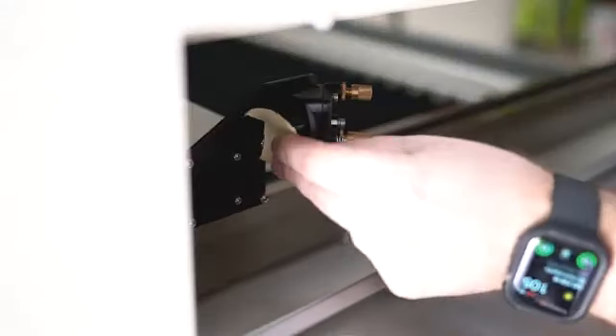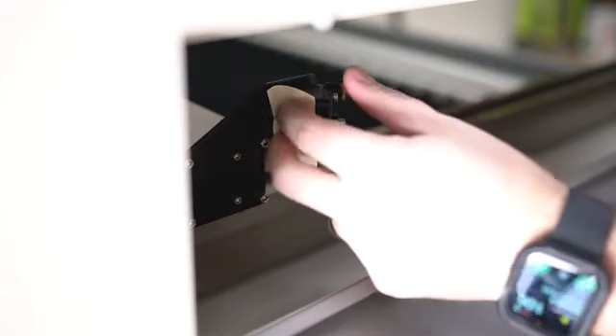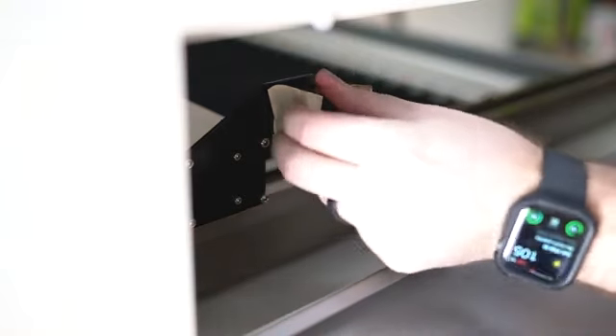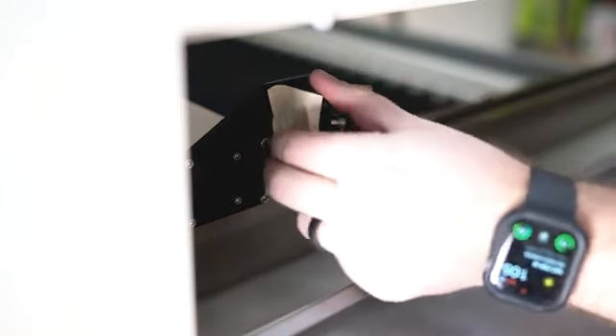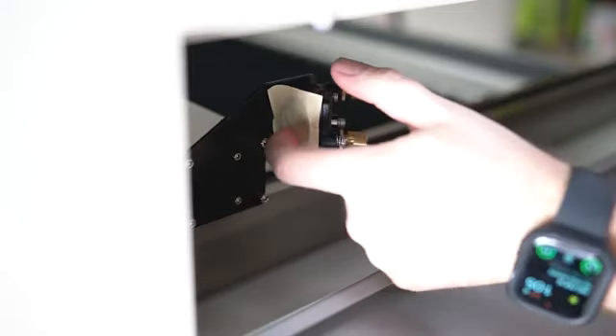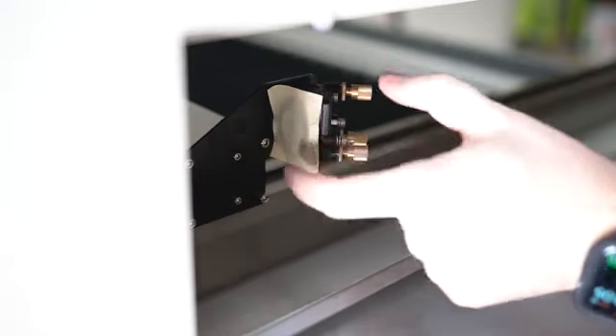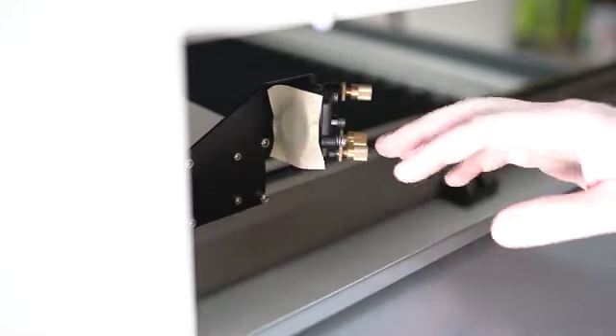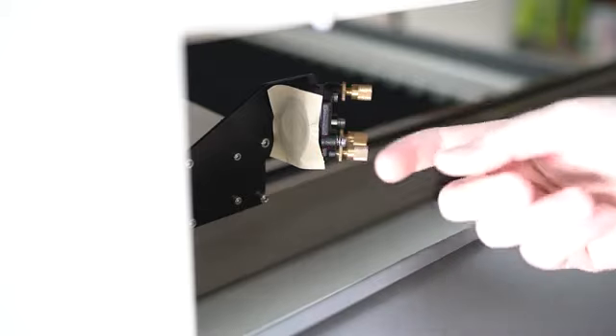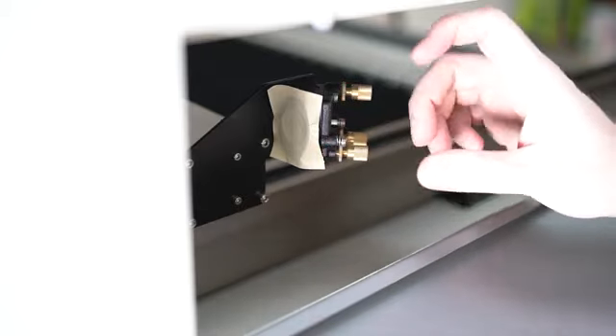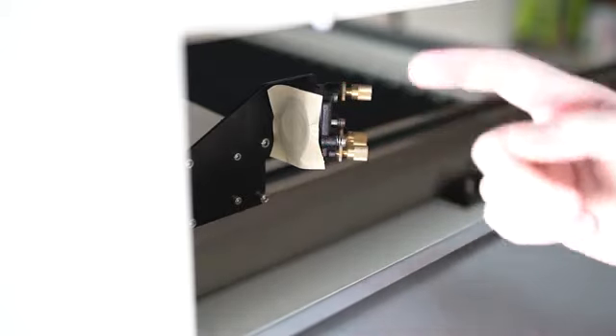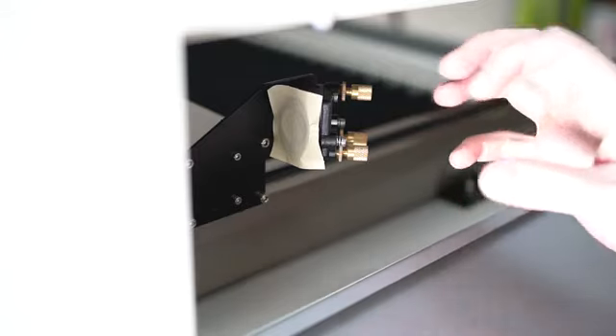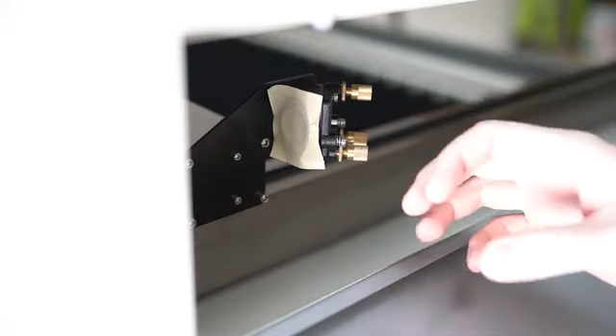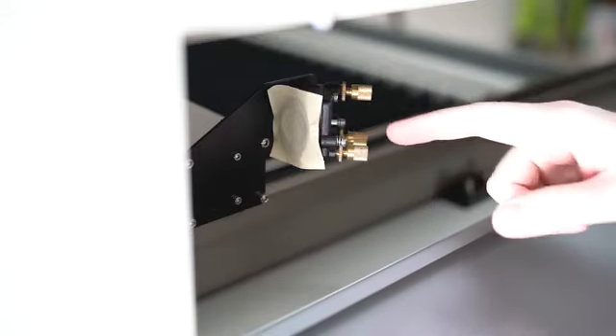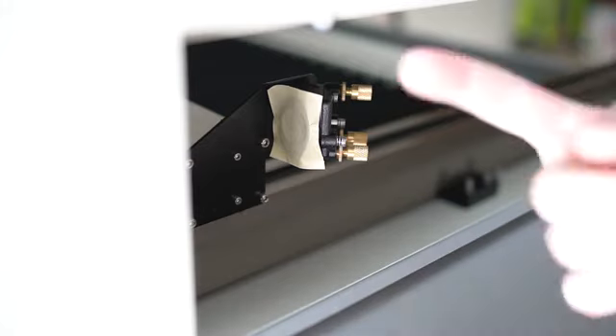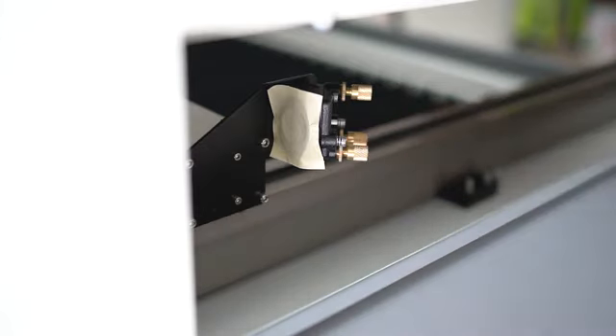We're gonna take a piece of tape, apply it over the opening here, and press down pretty good to make sure that opening is visible on the tape. You can see the hard outline of the opening. And what we're testing with this one, the first one was testing to make sure out of the laser tube that the height and everything, the position of that previous mirror was in place, basically just the housing. What we're testing with this test is to make sure that the alignment of that back mirror is correct.